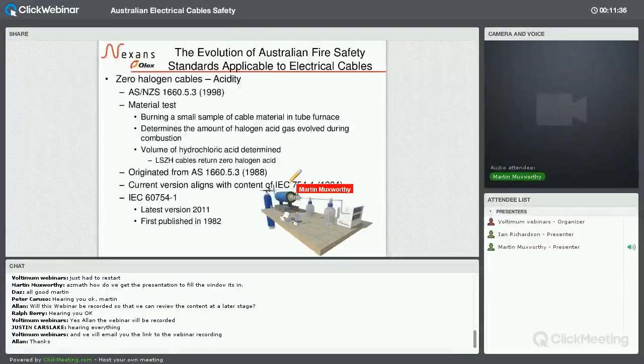So we've talked about how we measure the smoke that's given off by cables. There are some other tests that determine the acidity of the smoke, and believe it or not, it sounds a little strange, but it is possible to detect and measure how much acidity is given off by a cable, and this involves burning a small sample again, inside an enclosed, what they call a tube furnace.